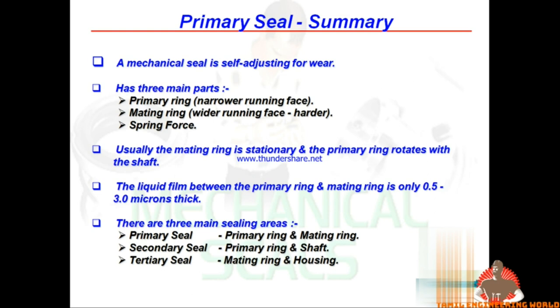The main parts are the primary ring and the mating ring. If you have a leak in the primary seal, it can involve the mating ring. The liquid film thickness between the primary ring and mating ring is 0.5 to 3 microns. There are three main paths where leakage can occur.